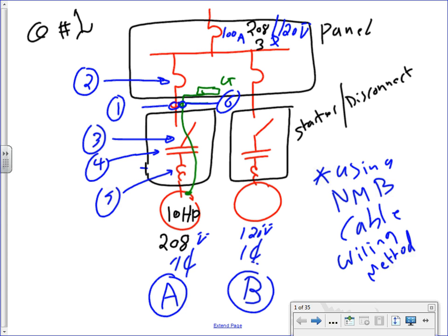If you don't have this graphic, guys, it will be a PDF on the network for you, so don't sweat it too hard. Just understand it. We have a starter disconnect combo sitting right there on that desk. That's what we're sizing. There's one little disclaimer: we are using the worst cable that you can ever imagine, which is NM cable. That will force you to use the 60-degree column from the get-go.